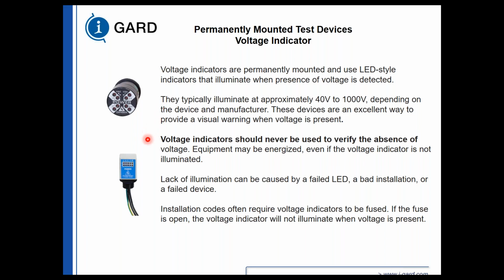Voltage indicators should never be used to verify the absence of voltage because they do not work if the voltage is less than 40 volts. So if a light is out, that doesn't necessarily mean it is de-energized. Lack of illumination can be caused by a failed LED, bad installation, or a failed device. Installation codes often require voltage indicators to be fused, so the fuse can be blown. And if the fuse is blown, you're not going to get any indication on the LEDs.